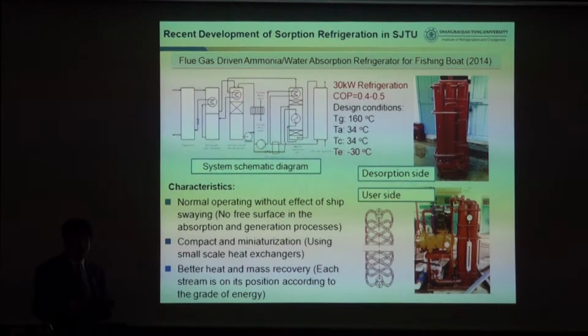But for an ammonia water system, normally you need a liquefaction column, because ammonia is dissolved into water. When you generate, you also bring some moisture, some vapor, so the ammonia is not 100% ammonia. It could be 95%. In this case, some water will come in with the refrigerant. So if it goes through a throttling process to a temperature below 0 degrees, there will be ice floating. So we need a liquefaction column, and the ammonia needs to be purified. But during the liquefaction process you generate some heat, and this heat could be used in the process. So we made use of the liquefaction heat, and in this way we tried to improve the COP of the refrigeration.